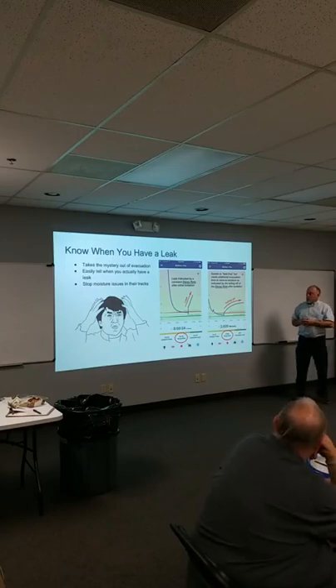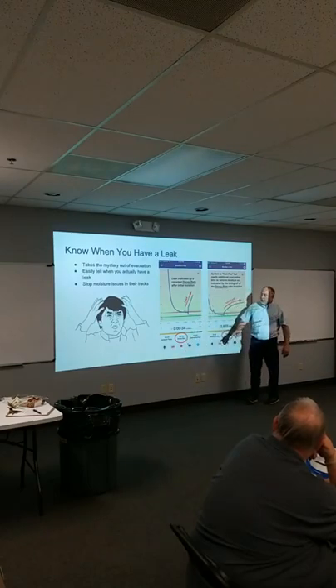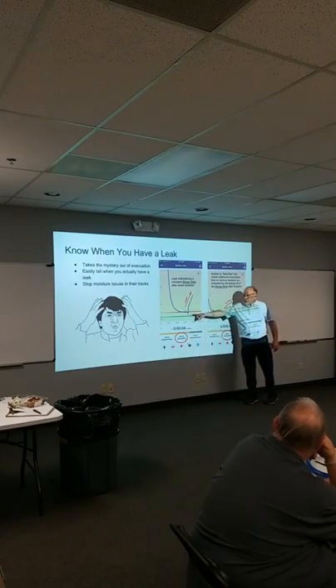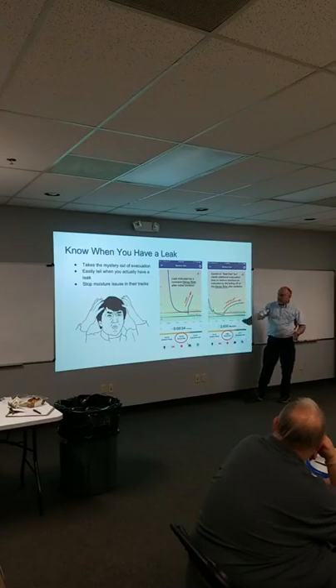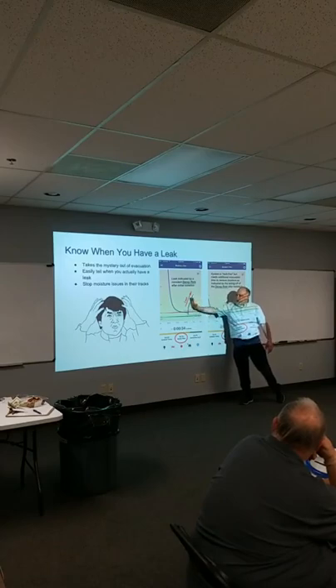So in the app, when you press this button, this valve down here, and isolate it, I had the guys change it from logarithmic to linear. So this is a linear graph right now. As soon as it goes to linear, now I can see that if I have a leak, as soon as I isolate it, the only reason this is not straight up is because it's over time, right? Otherwise, this would just be a straight up leak, okay?